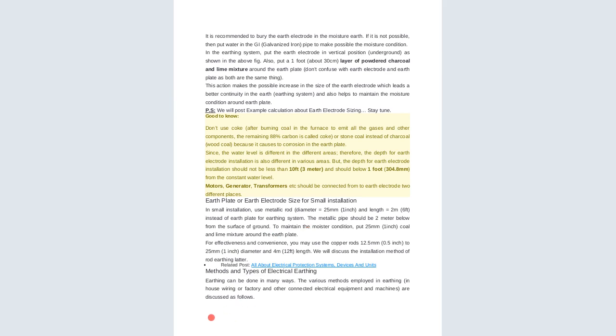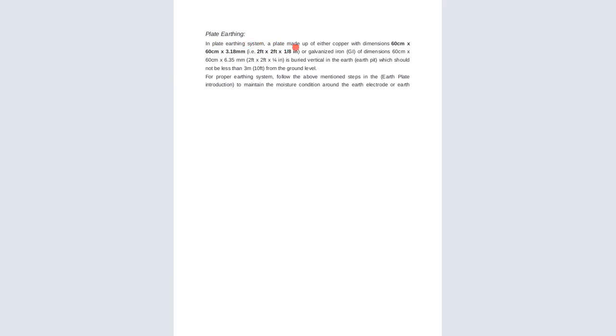The methods and types of electrical earthing. Earthing can be done in many ways. There are various methods employed in earthing in a house, factory and other connected electrical equipment and machines, discussed below. We have plate earthing, which we had already talked about. In this system, plates are made of either copper with dimensions of 60 centimeters by 60 centimeters by 3.18 millimeters, that is 2 feet by 2 feet by 1/8 of an inch, or galvanized iron GI of the dimension 60 by 60 by 6.35 millimeters.